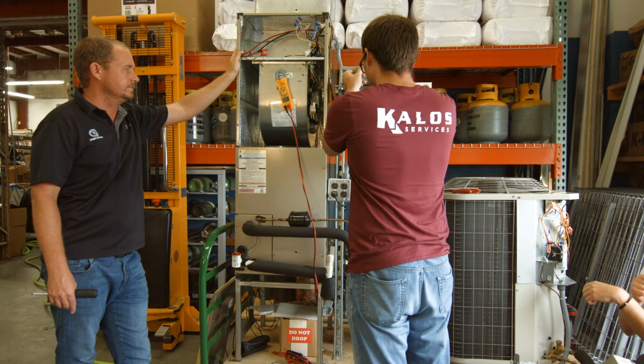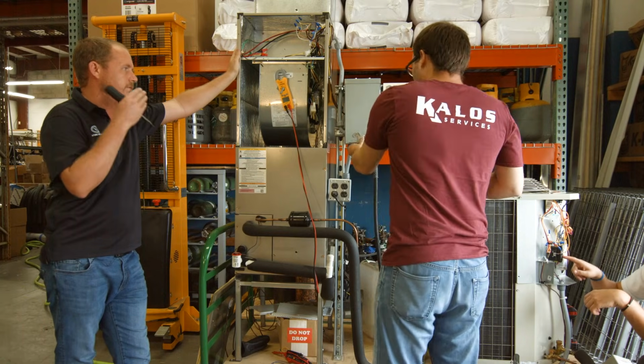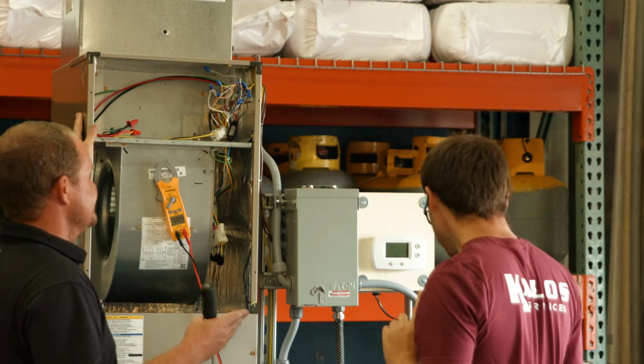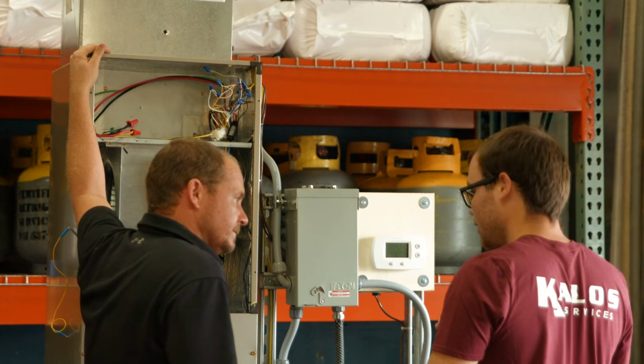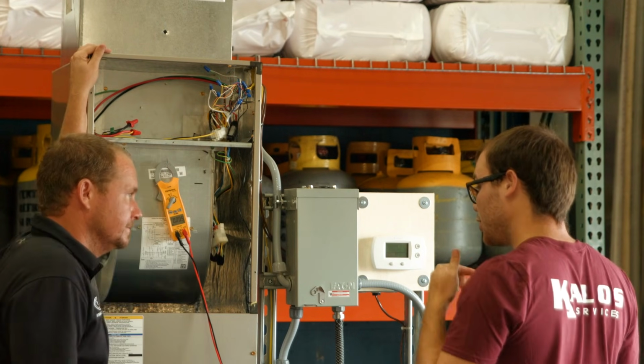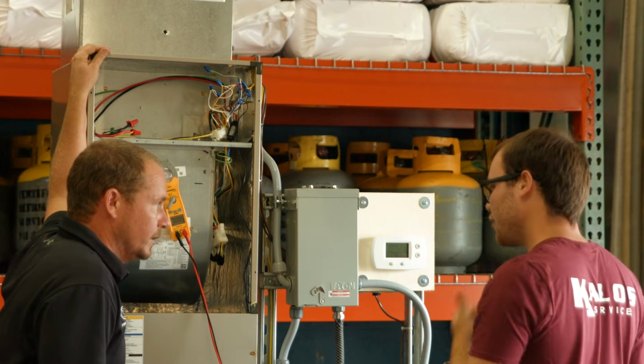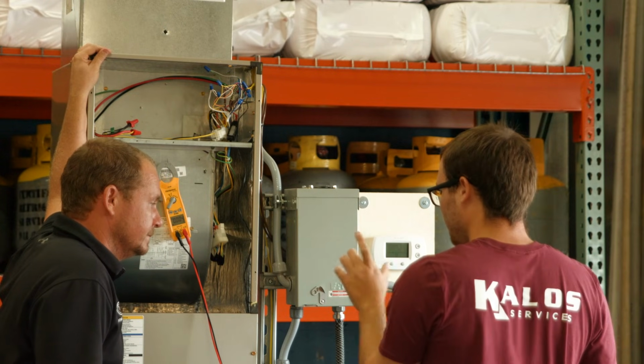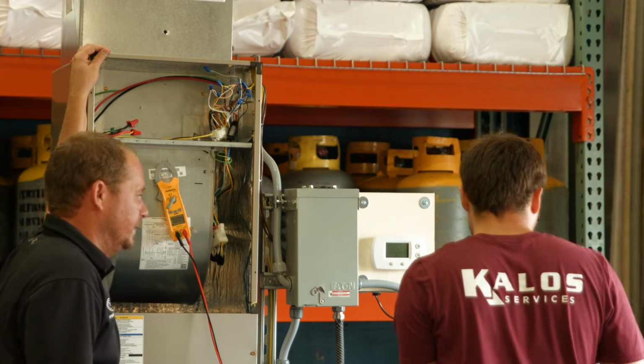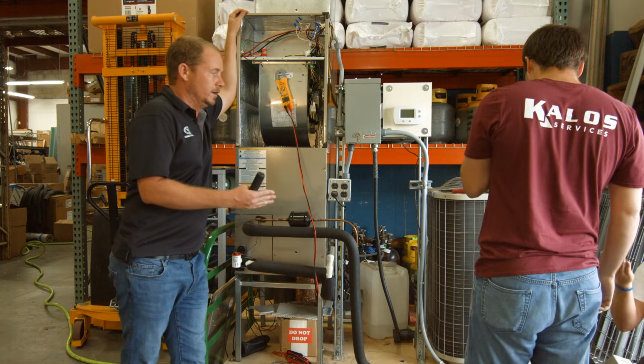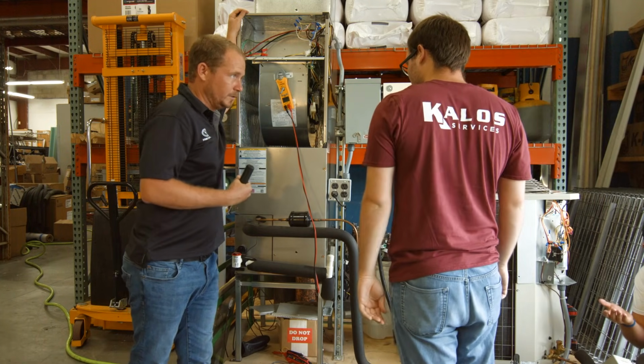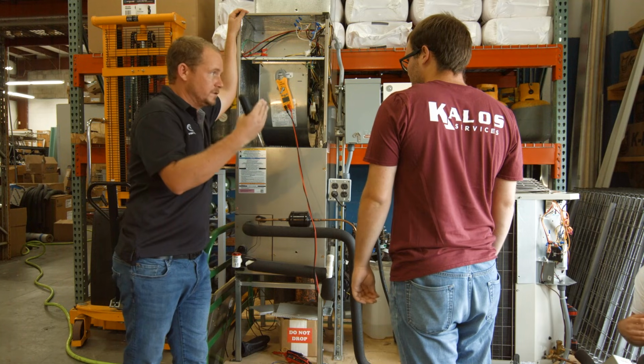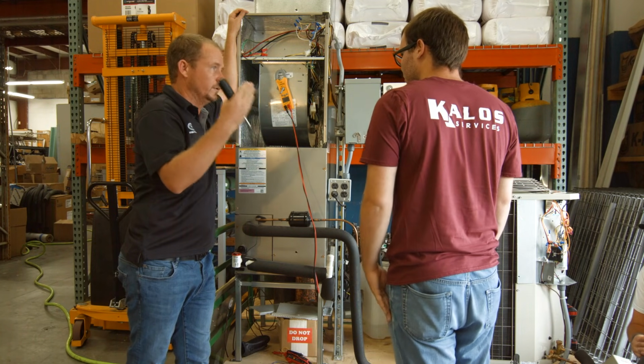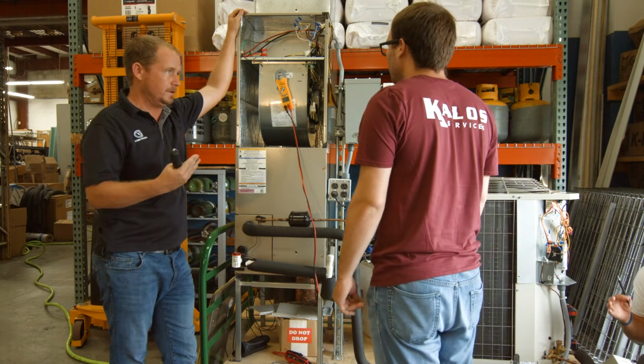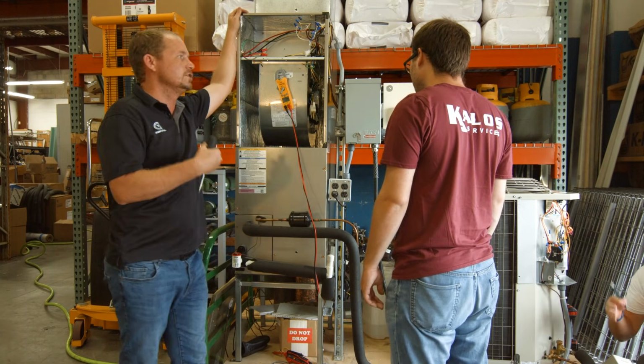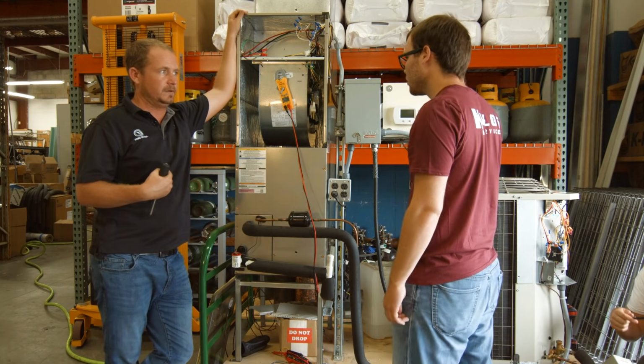All right, so what's the conclusion? Well, so far I know that the orange is not energized. The reversing valve should be getting energized to turn into cool. That's not happening. This turned on fully, so I'm not going to look at it. The blower turned on. Yes. Compressor contactor pulled in. Yes. Reversing valve did not. The solenoid is not energized, so it's running in heat mode. All right, so what energizes the reversing valve solenoid?